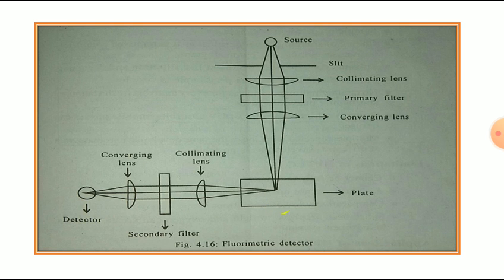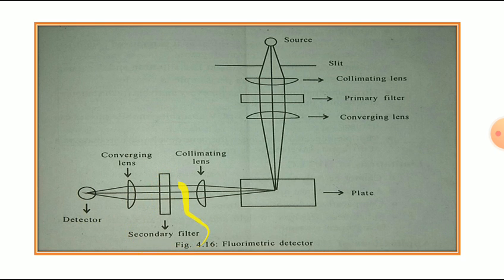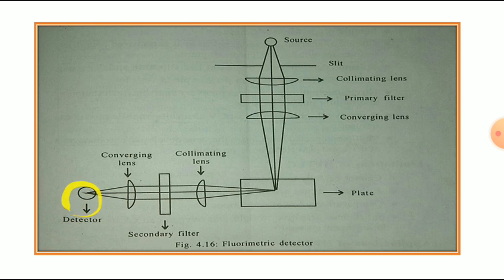The sample component absorbs the UV light and emits fluorescence radiation. That fluorescence, emitted at a right angle to the incident beam, along with any remaining UV, passes through a collimating or converging type of lens and falls on the secondary filter. This secondary filter absorbs the UV and passes only the fluorescent radiation emitted by the sample component. That fluorescent radiation passes through a converging lens and falls on the detector. The detector calculates and creates a characteristic net signal, which along with the blank reading, shows the chromatogram in the recorder. This is the fluorometric detector.